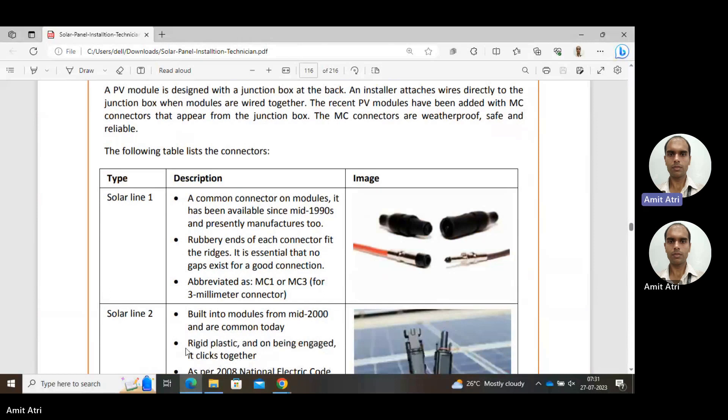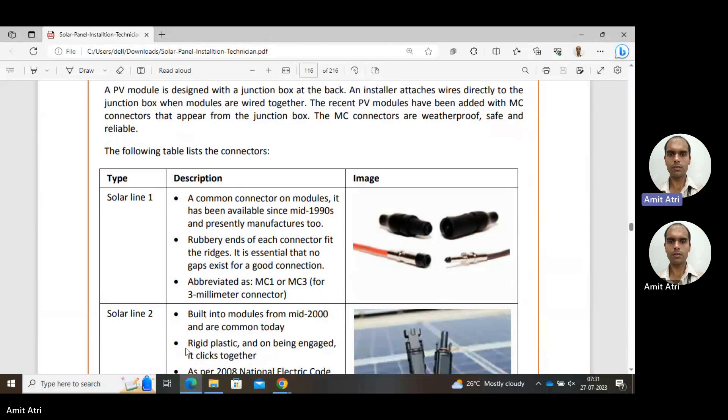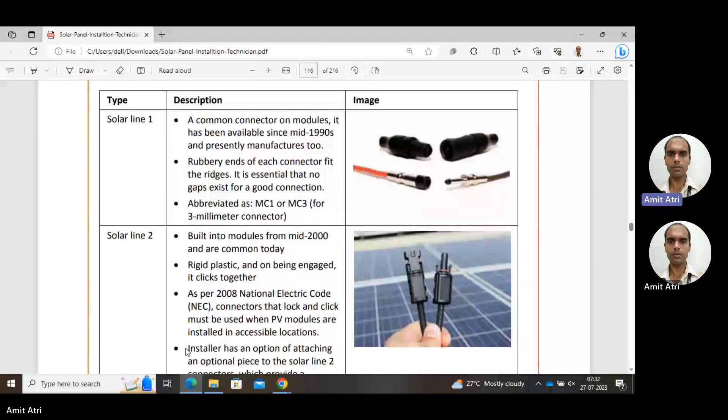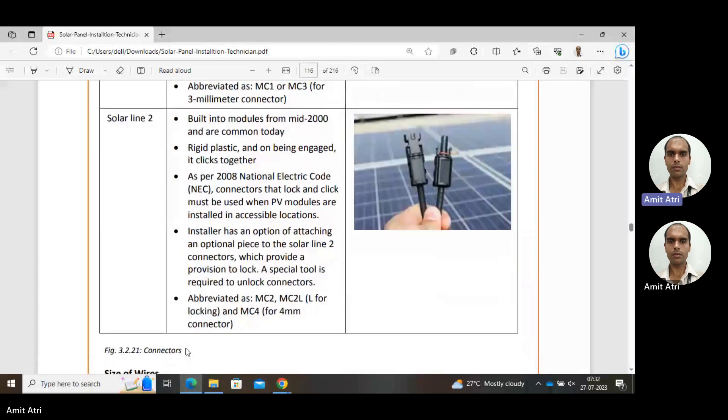Recent PV modules have been added with MC connectors that appear from the junction box. The MC connectors are weatherproof, safe, and reliable. Solar Line 1 shown in the image is a common connector module, an earlier version from 1990. It is still used but not much. The rubber end of each connector fits the ridges. It is essential that no gap exists for good connection. Gap means chances of leakage and sparking. It is abbreviated as MC1 or MC3.